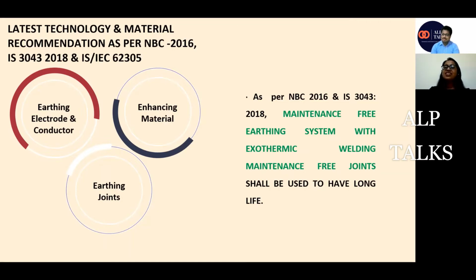Yeah, generally it happens. We do not have space, and the resistivity is such that we are not able to achieve the value. So what happens, we ask our end client what is the maximum space you can give us for installing the earthing system. You tell us your limitation, then we'll see how we can work around that. Suppose he tells us that you have 15 by 20 meters of area, or 20 by 20 meters of area. So that is fixed, that we cannot go beyond it.